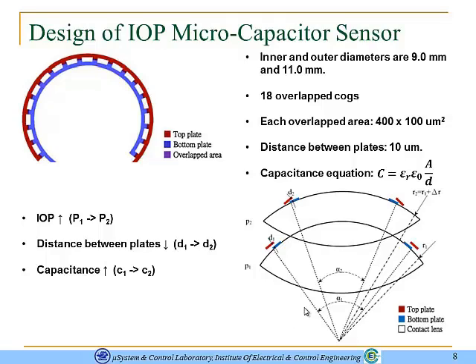When the IOP increases, the contact lens will move on the surface of the cornea, and then it bends and follows the corneal deformation. When the IOP increases, the distance between the top and the bottom electrodes will decrease. Then my capacitor value will increase.